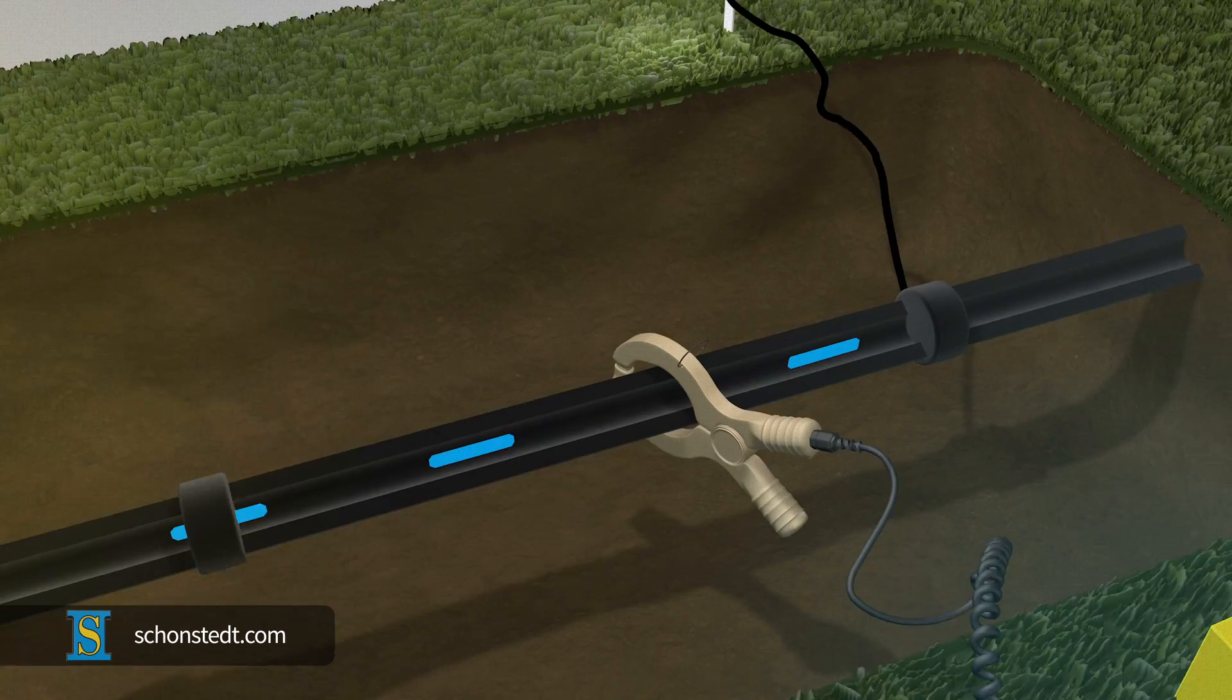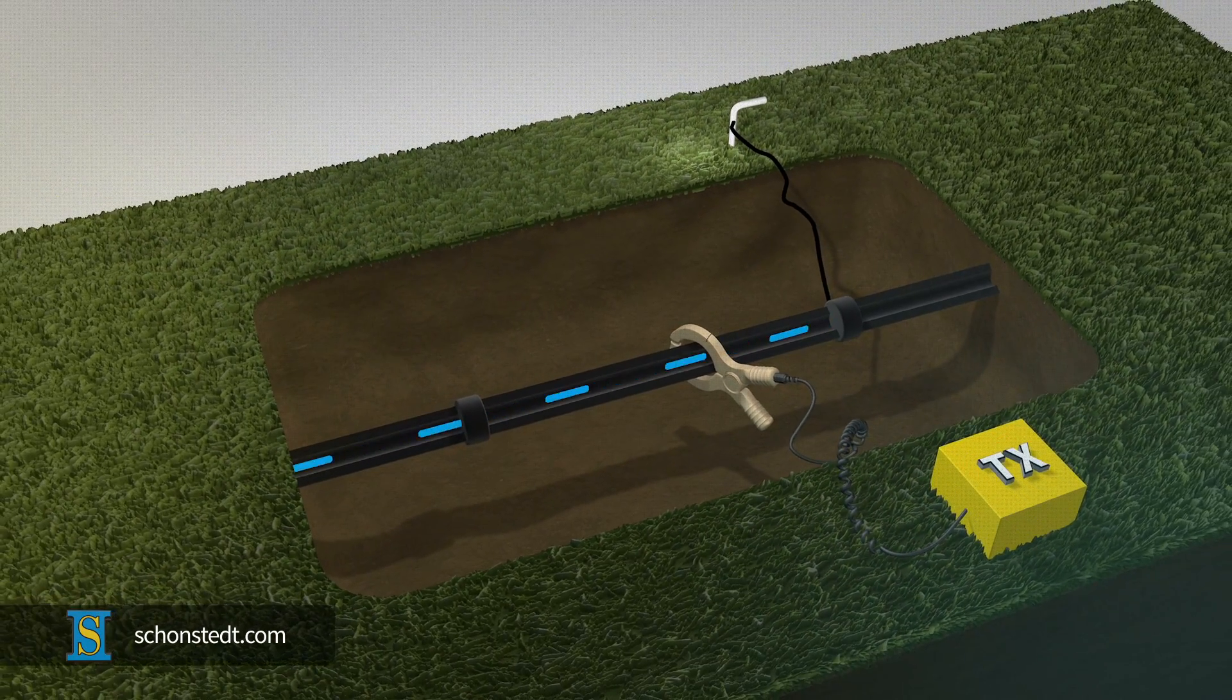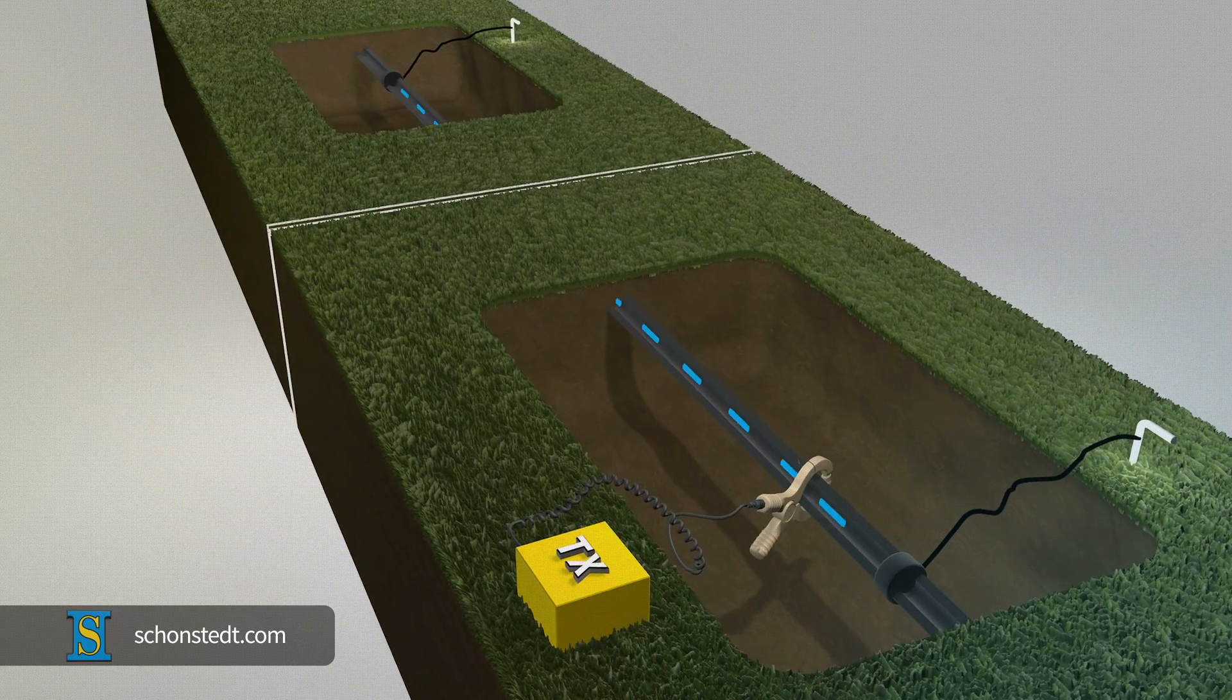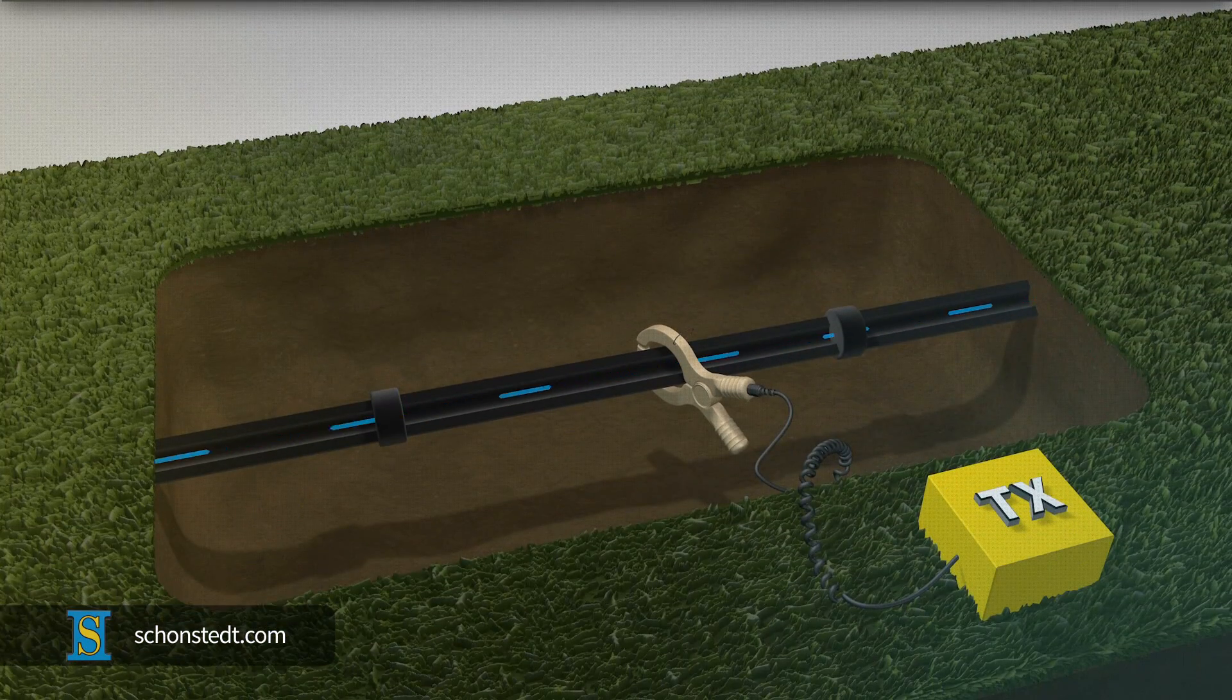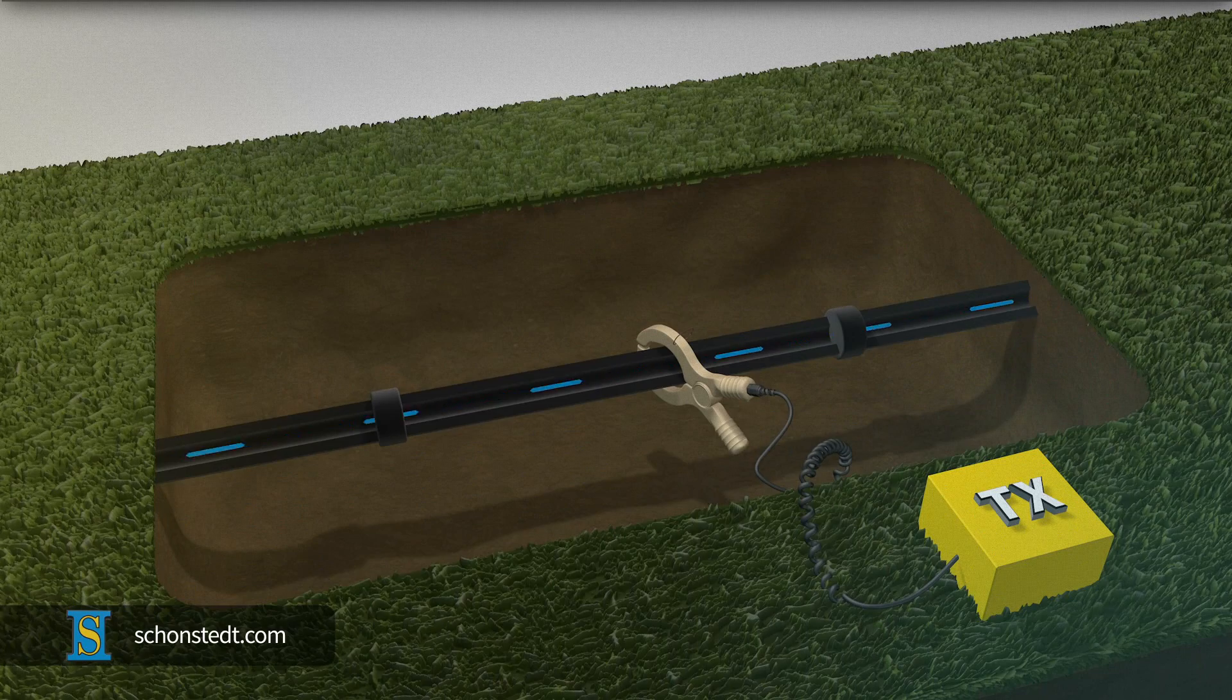At least one end, but preferably both ends – the near and far of the pipe or cable – must be well grounded. Without a ground, the current will be extremely low, which will make locating nearly impossible.